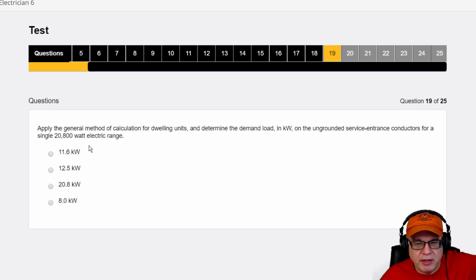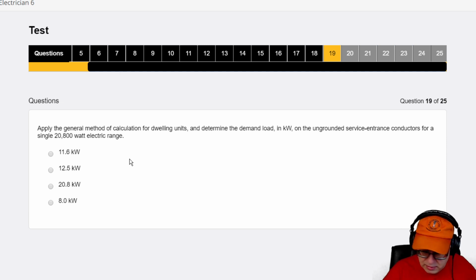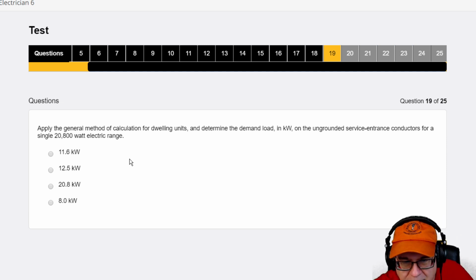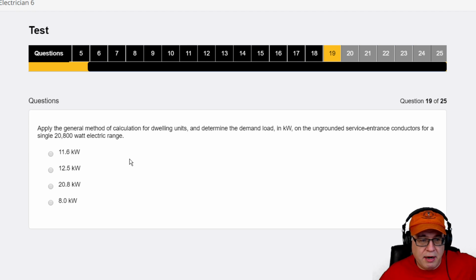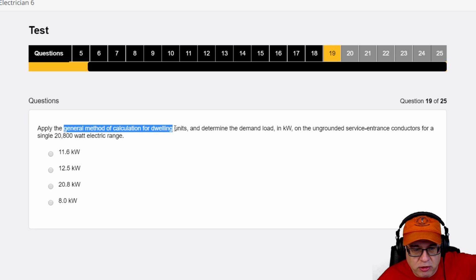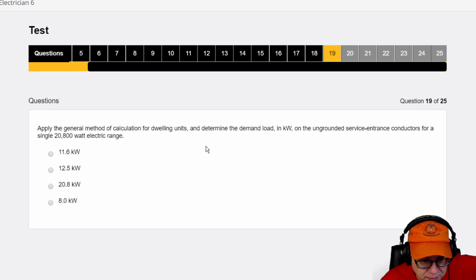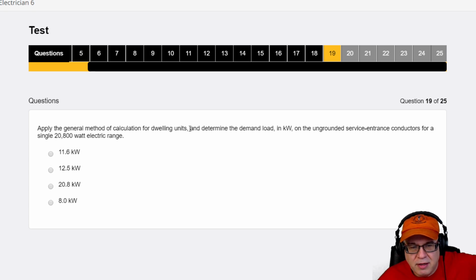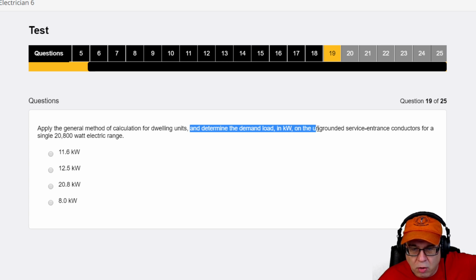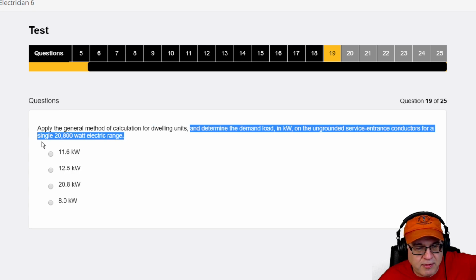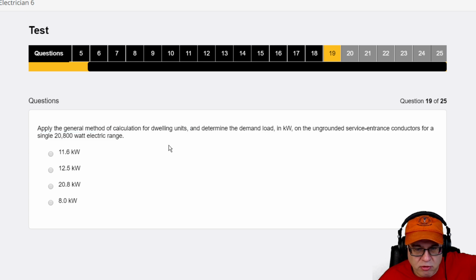All right, let's look at this one, and I'll end on this one tonight so everybody can get to bed at a decent time. Apply the general method of calculation for a dwelling unit. When we say general, I'm thinking it means the standardized method. Determine the demand load in kW on the ungrounded service conductors for a single 20,800 watt electric range.